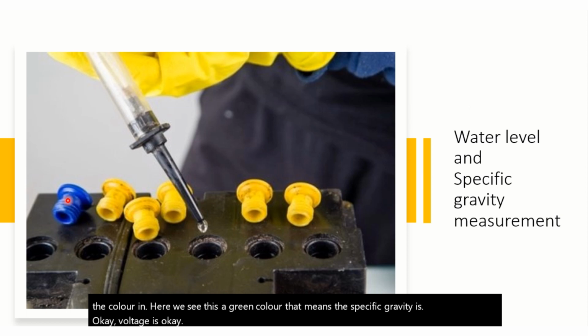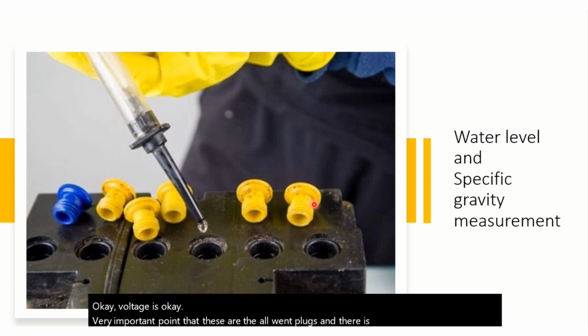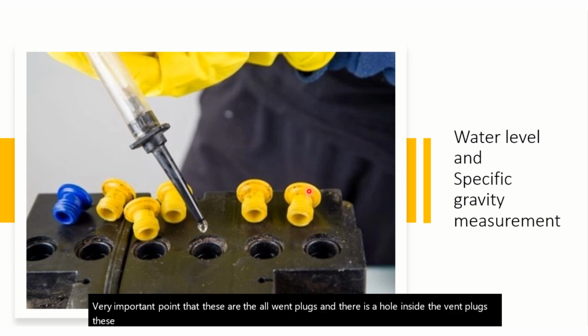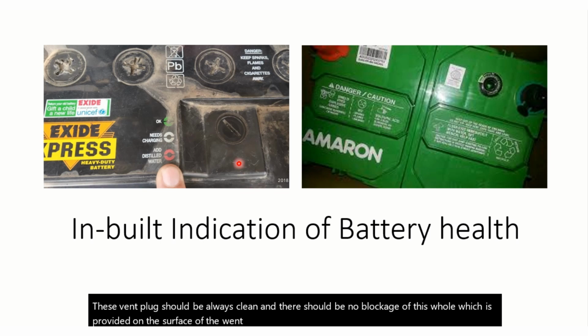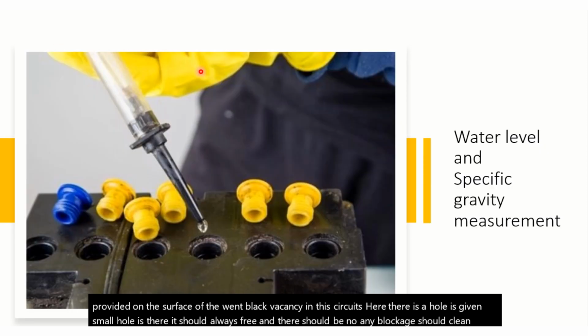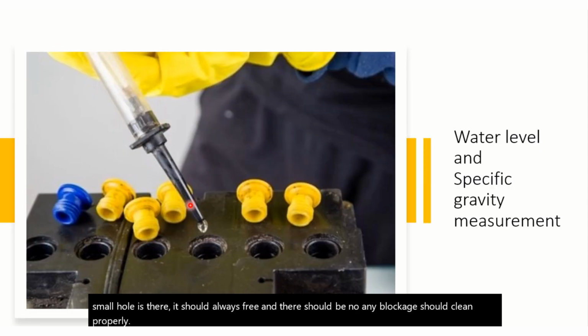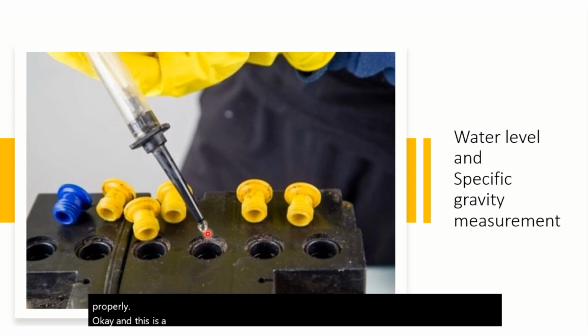A very important point: these are all vent plugs, and there is a hole inside the vent plugs. These vent plugs should always be clean, and there should be no blockage of this hole which is provided on the surface of the vent plug. We can see in these vent plugs a small hole is given. It should always be free and there should be no blockage. It should be cleaned properly. Okay, and this is a hydrometer to check the specific gravity.